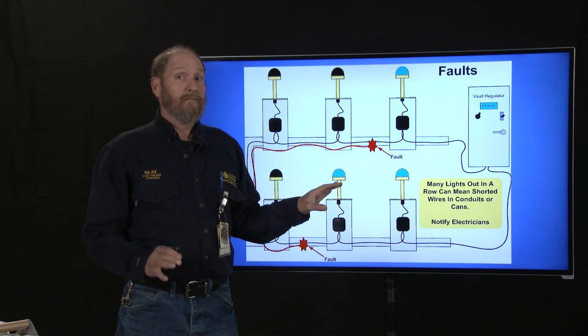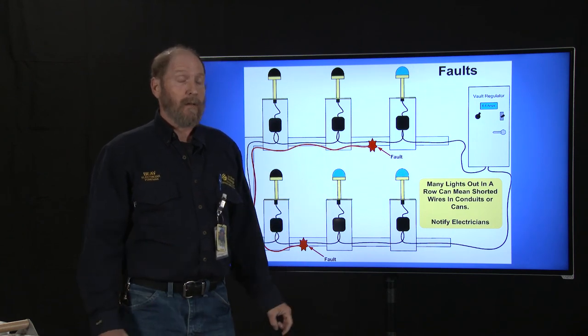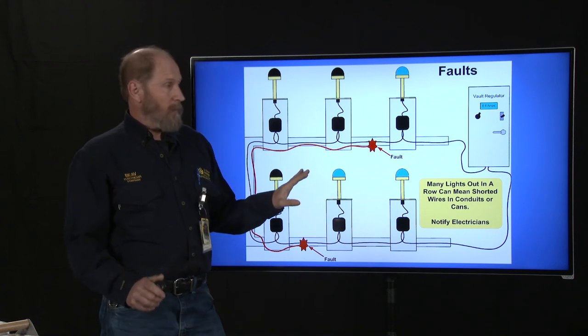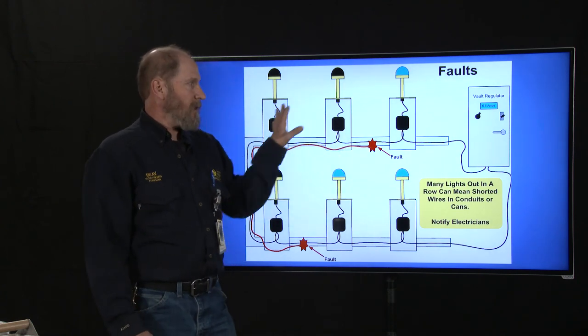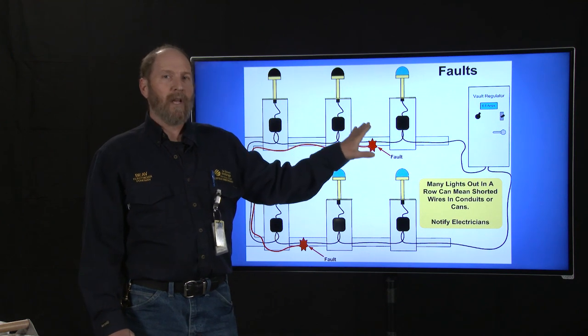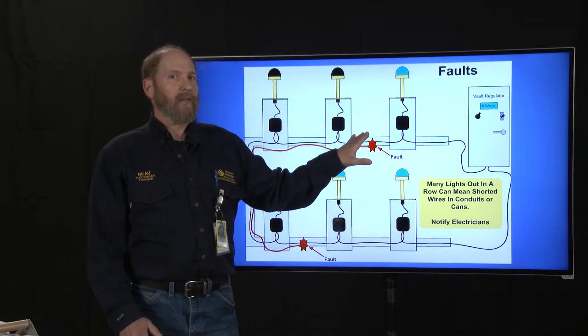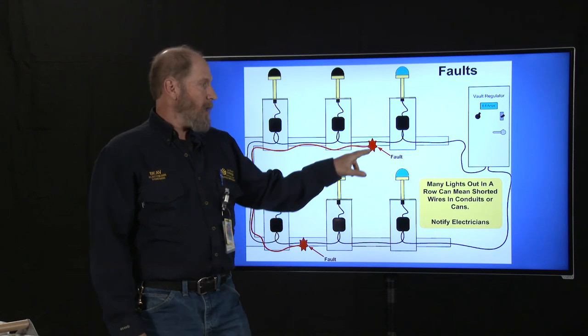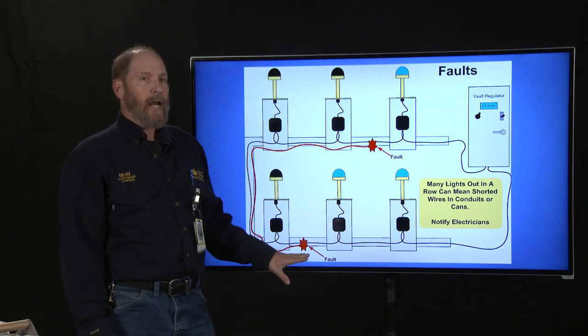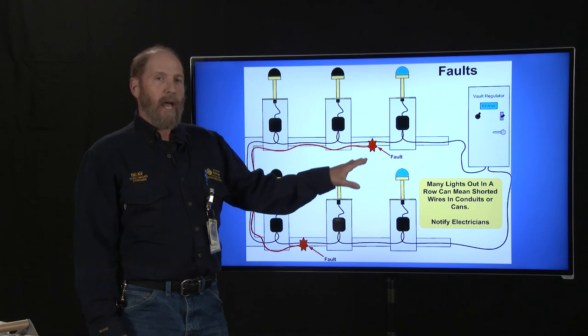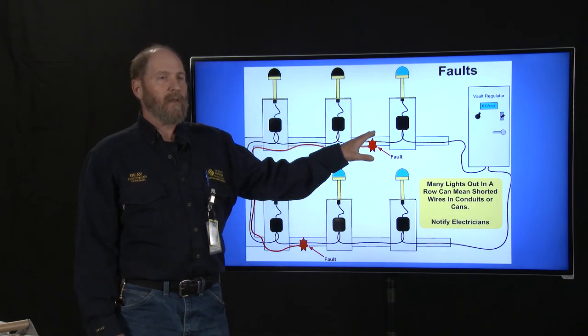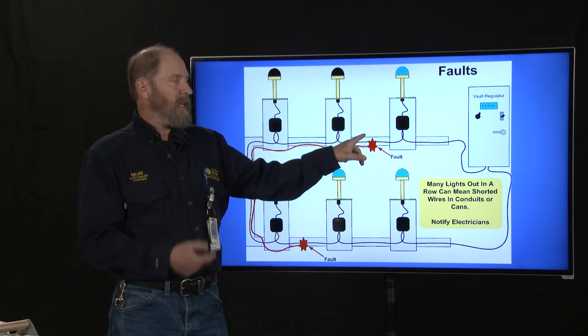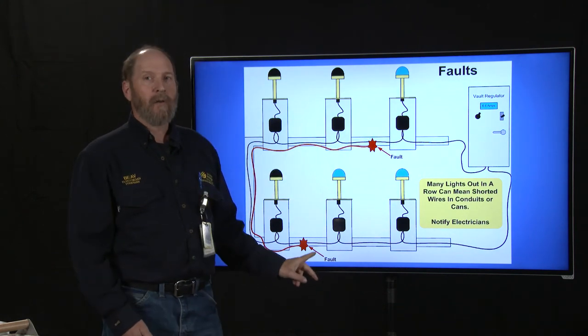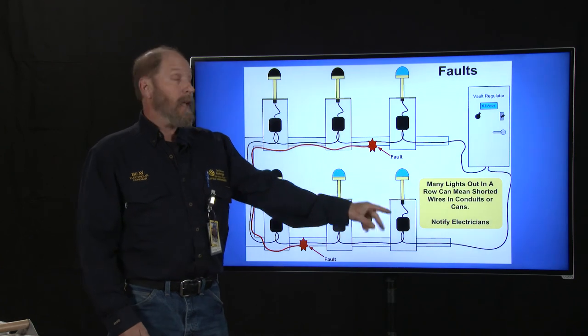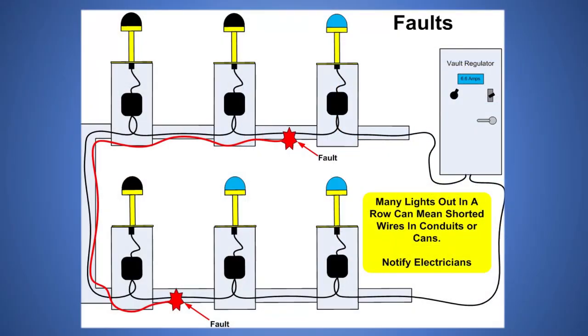But it's also a really stupid statement, and it's a good way to get killed. Because if everything in this system is perfect except for the one place that you touch that wire, yes, it will not jump through you. But if there is another fault out there anywhere on that system, and you touch that wire, you will become the second fault. It will use you to get to the ground system, to follow the ground, to get back into the system. And this constant current system will run all the lights right through you.